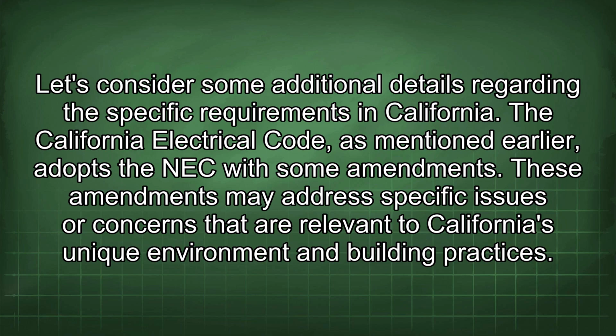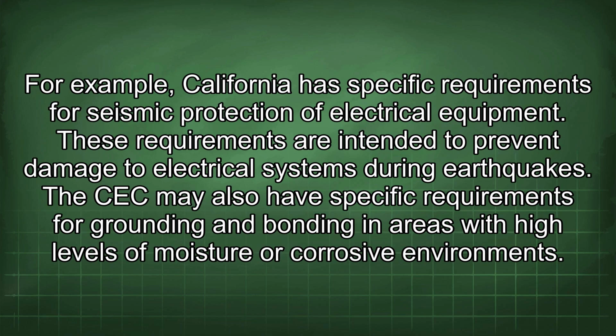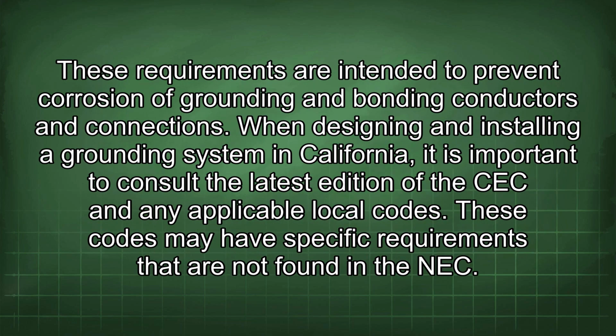Let's consider some additional details regarding the specific requirements in California. The California Electrical Code, as mentioned earlier, adopts the NEC with some amendments. These amendments may address specific issues or concerns that are relevant to California's unique environment and building practices. For example, California has specific requirements for seismic protection of electrical equipment. These requirements are intended to prevent damage to electrical systems during earthquakes. The CEC may also have specific requirements for grounding and bonding in areas with high levels of moisture or corrosive environments. These requirements are intended to prevent corrosion of grounding and bonding conductors and connections.